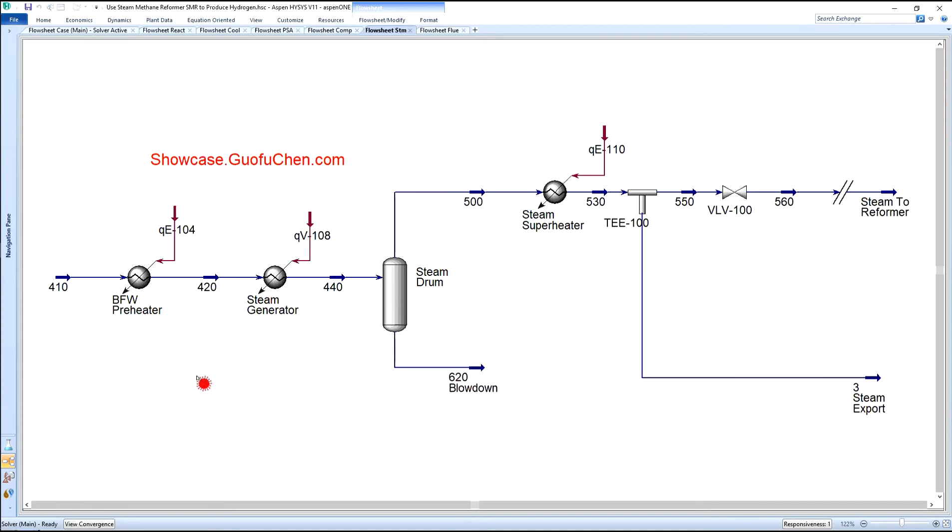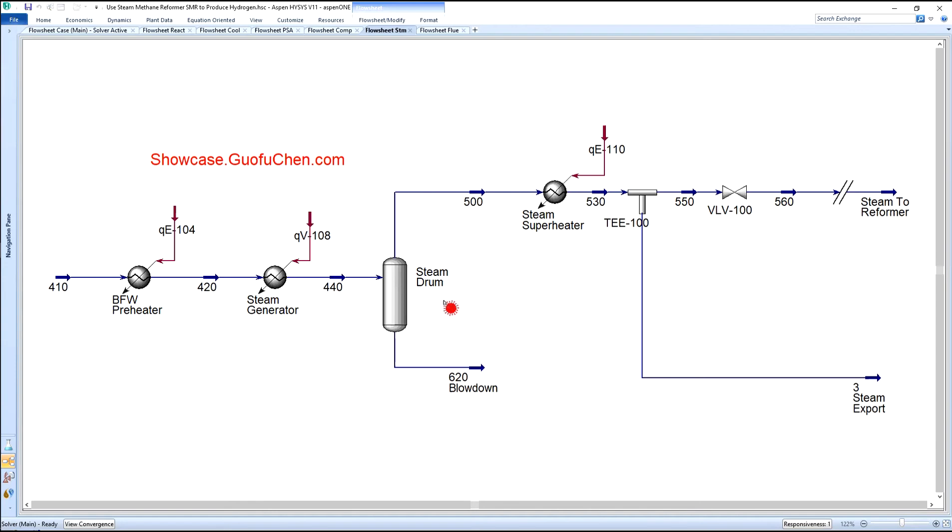The steam module is used to produce steam. The heat for boiler feed water pre-heater comes from the product gas mixture. The heat for steam generator comes from steam generator coil one, two, and three. The steam is further superheated by flue gas after blowing down a small quantity of liquid water.